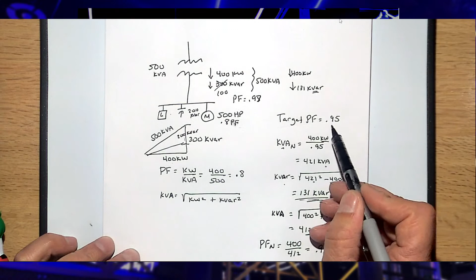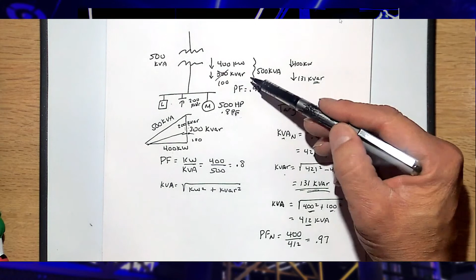If I had 300 and I put 200 in, I'm left with 100. So my new kVA is the square root of 400 squared plus 100 squared, 412 kVA. My new power factor, 400 over 412, is 0.97. My utility is billing me for 0.95, and I'm getting 0.97, so that's good. And my new power running through my system is 400 kW and 100 kVAR, so I have a total going through my transformer of not 500 kVA now, but 412 kVA.